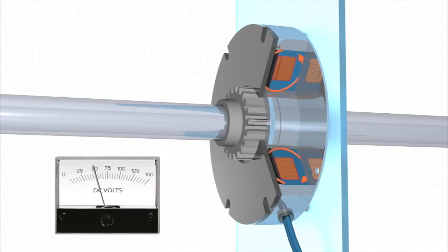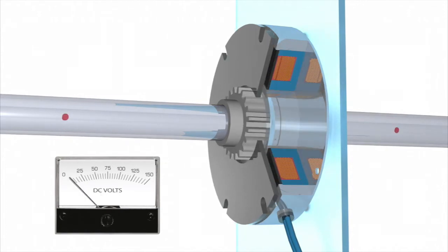Since most of the current is required to reach across the air gap to the pressure plate, once the pressure plate is engaged, current can be reduced significantly to reduce power consumption of the brake.